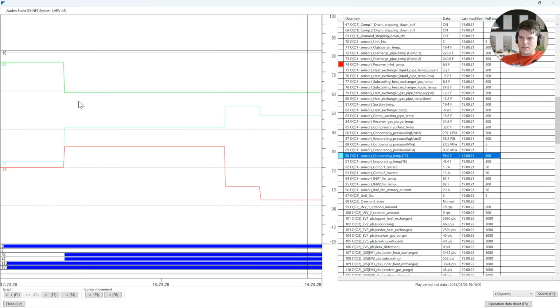What happened? This is the part where guys throw their laptops off the roof because none of this makes any sense. We're at 95-degree liquid temp, but wait a minute, my receiver temp is 6.8. Holy crap, I just subcooled the crap out of this refrigerant. This subcooler is insane. But wait a minute, there's no subcooler involved in this spot. That's why we're taking this temperature. Well, how do I have 6.8 degrees on my receiver temp and also a 95-degree saturation temperature? That subcool is off the charts. But is it though? This is where I enter that meme, "Is it really?"